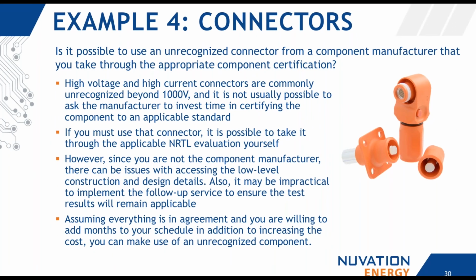And also, when it comes to connectors, a question that comes up is whether it's possible to use unrecognized components that we end up taking through component certification. For applications beyond 1,000 volts or 100 amps, it's hard to find connectors available on the market. It's much more common to find unrecognized components for these applications. But the manufacturers of these connectors are busy, and so it's not always easy or possible for them to invest the time in certifying the component.